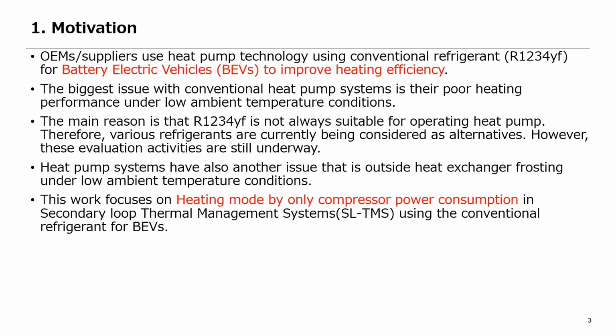First, let me discuss the motivation behind our study. Lately, both OEMs and suppliers have been adopting heat pump technology, specifically using the conventional refrigerant R1234yf, to enhance the heating efficiency of battery electric vehicles. However, a significant challenge with these conventional heat pump systems is their diminished heating performance in colder ambient temperatures. The primary issue stems from the fact that R1234yf isn't always the best choice for heat pump operations. Consequently, there's ongoing research exploring alternative refrigerants. Another concern with heat pump systems is the potential for the external heat exchanger to frost up in colder conditions.